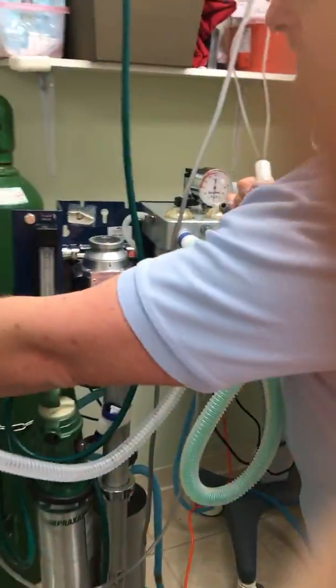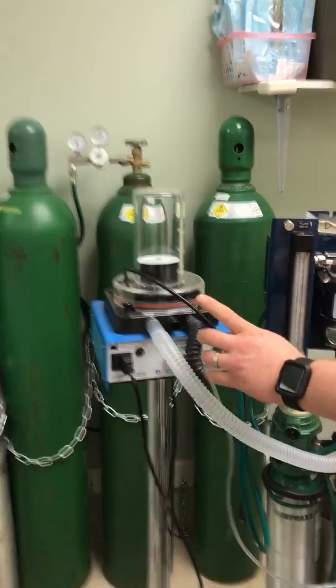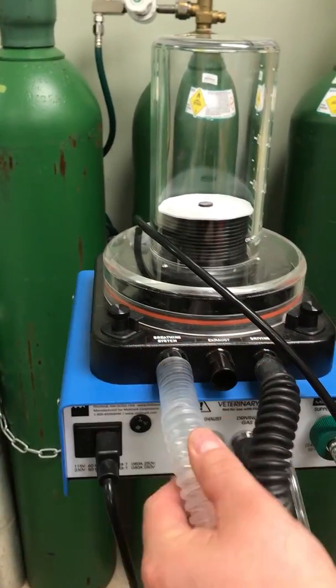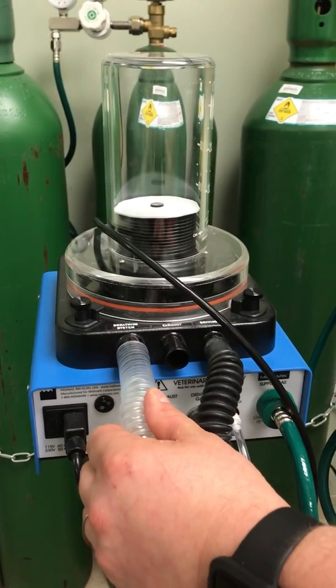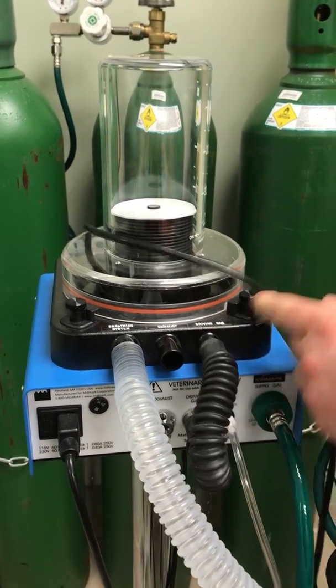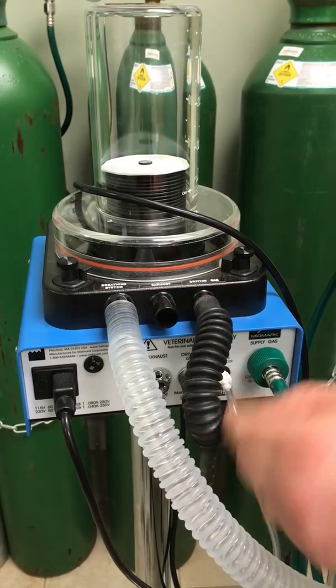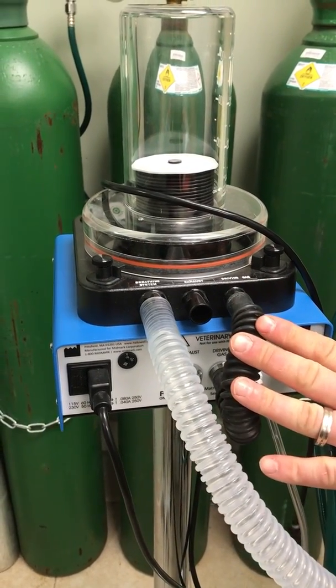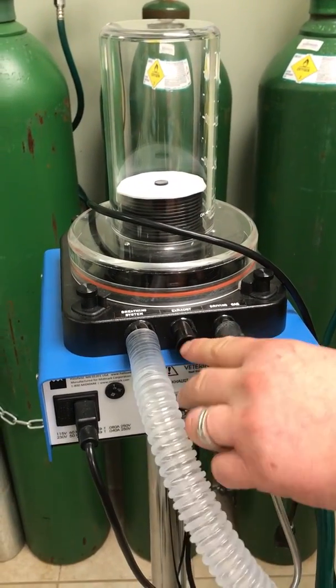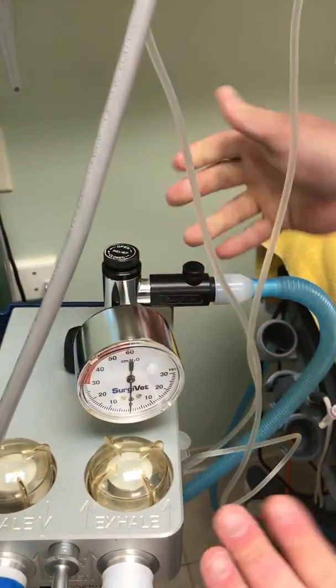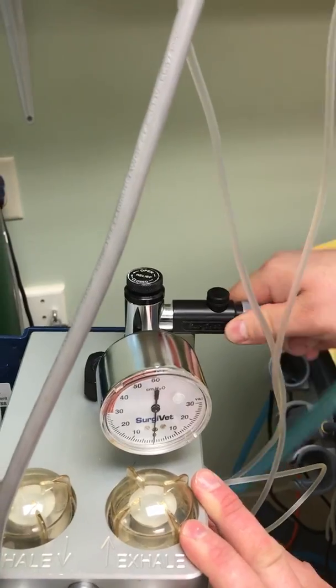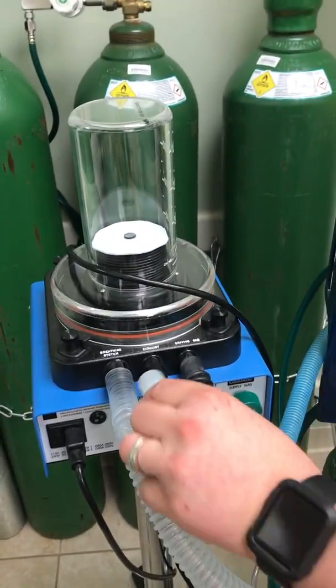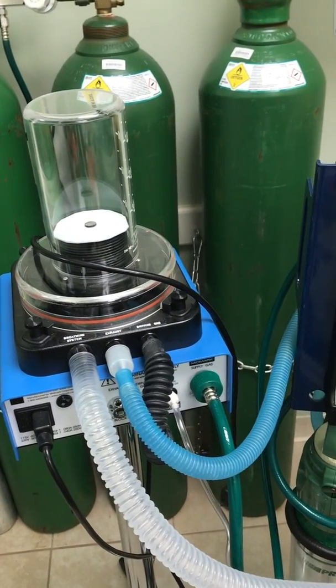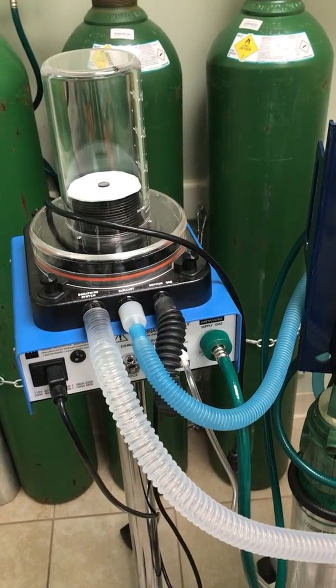So the other hoses back here, you've got your breathing system we hooked up to where the rebreather bag came. We've got the driving gas, it says. We don't touch this. It stays there always, so we don't want to remove that. And then we have exhaust. And exhaust is where your exhaust goes. So we take it off of the exhaust from our anesthesia machine, and we attach it to the exhaust from the ventilator machine.